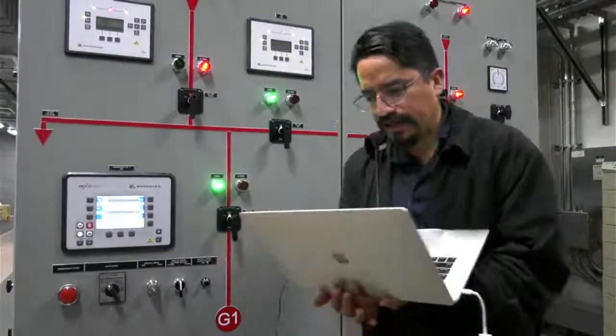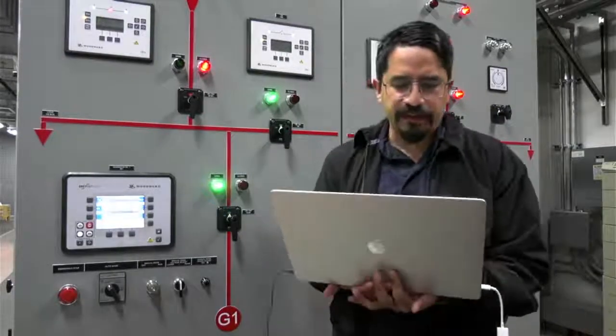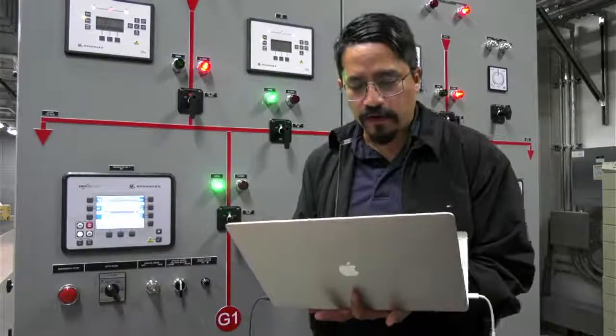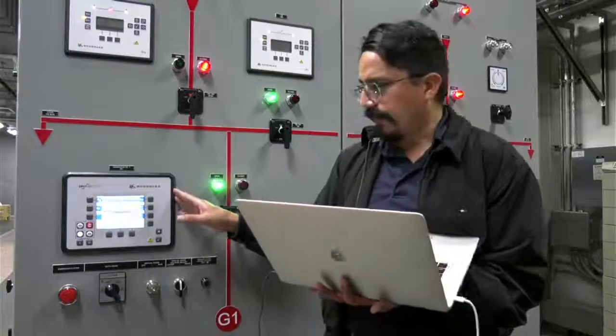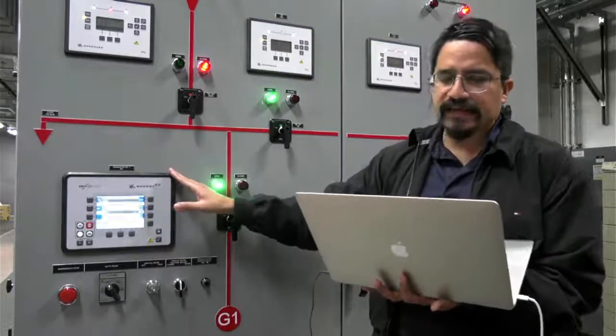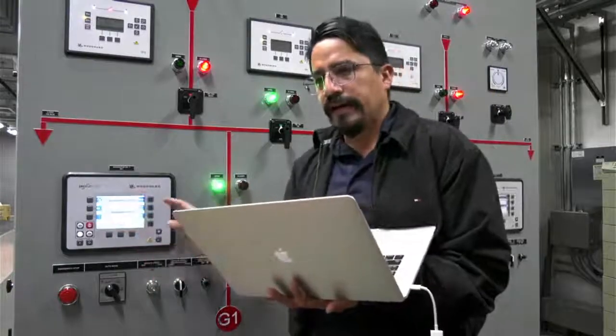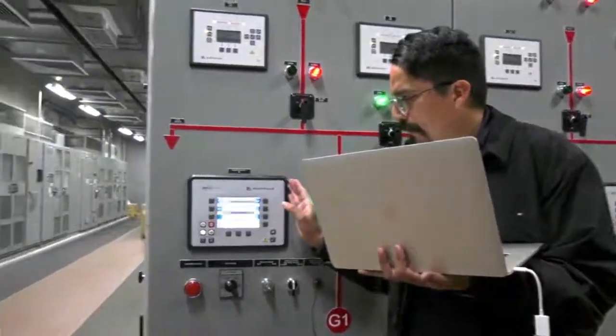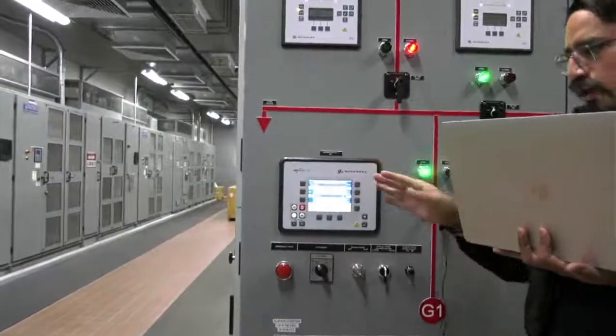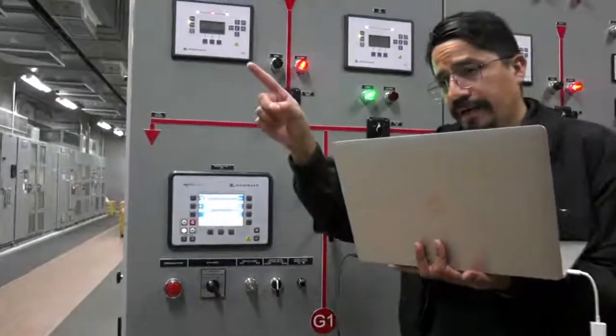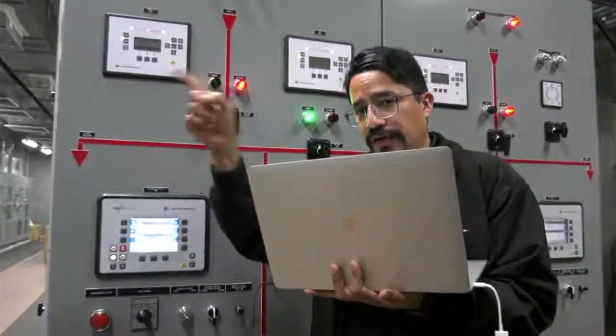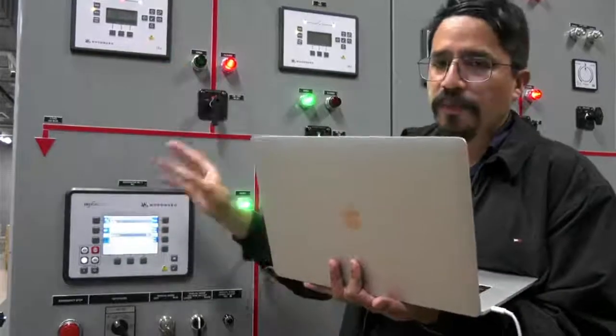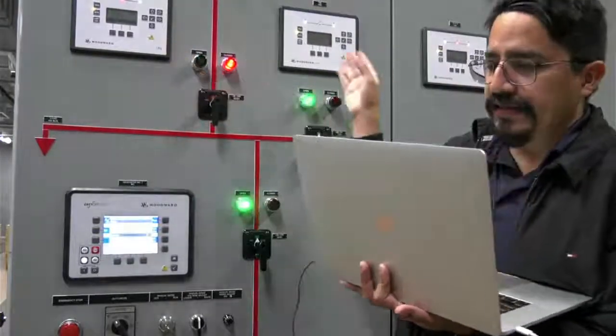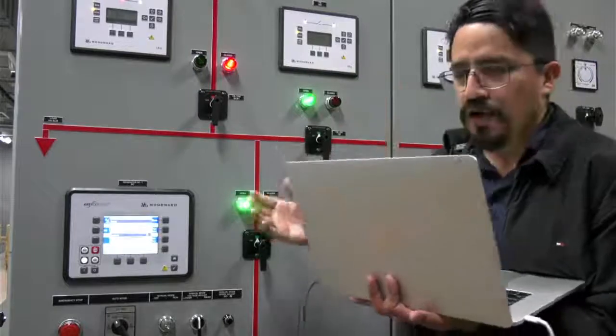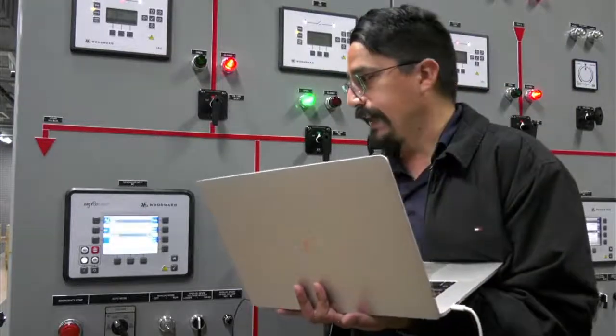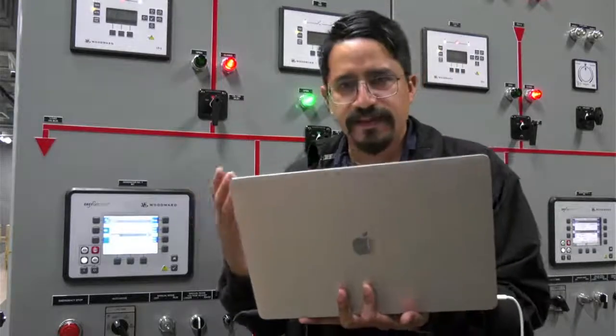Okay, I'm looking at sheet 29, and I'm going to explain a little bit of group number 4. Group number 4 is comprised of EasyGens. The EasyGens, as I said, is the main generator control. It has all the configuration and programming, and basically talks to everyone. It talks to the caterpillars, controls the voltage and the frequency to the caterpillars, and talks to each component here, meaning the TCOs, the tiebreakers, so it knows what's happening all the time, and it can take different actions depending on what's the available source.